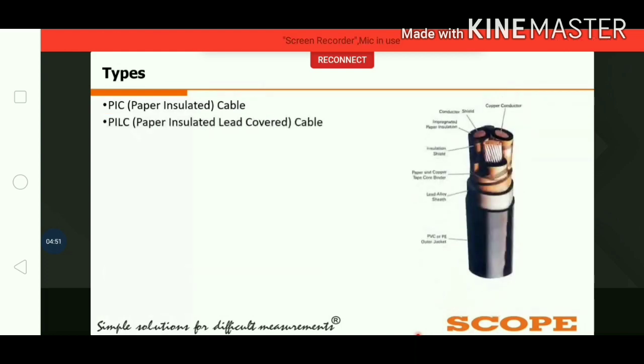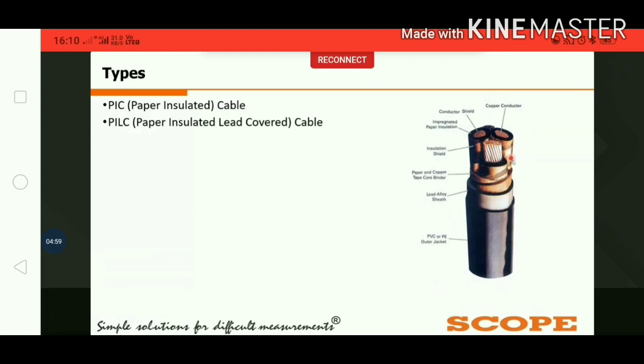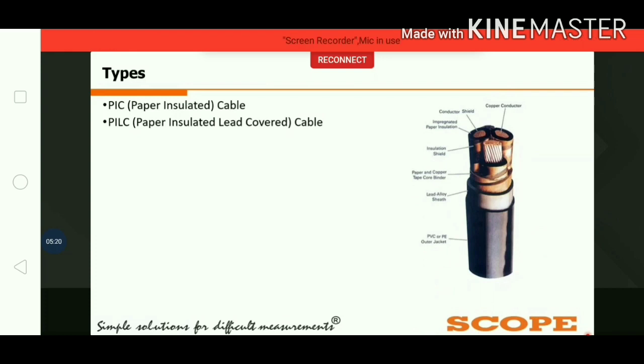In PILC (Paper Insulated Lead Cover) cable, as shown in the picture, the core is surrounded by a separate lead sheath. This lead is used to prevent the entry of moisture into the cable, and this was mainly developed to overcome the disadvantage of plain paper insulated cables. These cables were mainly developed around the 1940s to 1950s and are used for medium voltage applications.